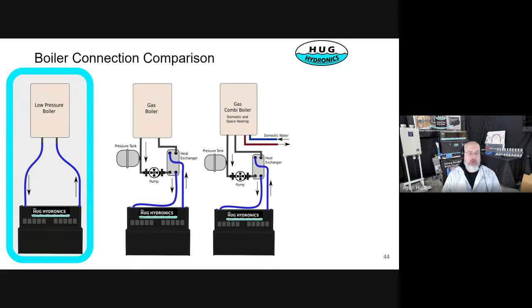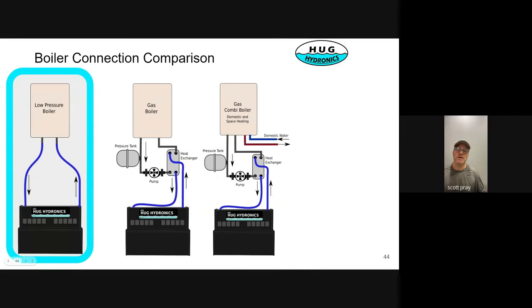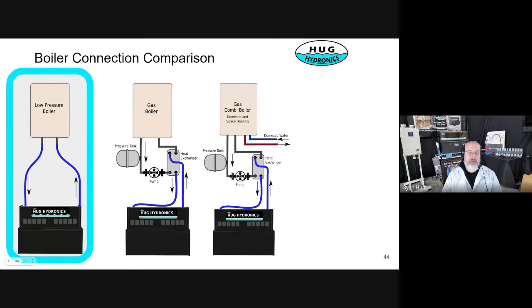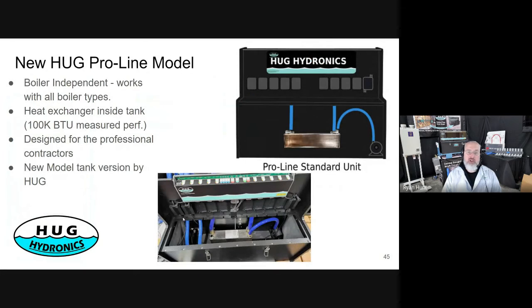But generally, you'll probably want to run them a little hotter so that it warms the tank up, because the minimum setting on the high pressure systems is like 120 to 125 typically. Yeah, then they step it down. So a low pressure boiler here. This is our streamlined plumbing. Boilers that require pressure require a heat exchanger in the system. They have a heat exchanger loop, and then we take our heat off the other side of the heat exchanger.